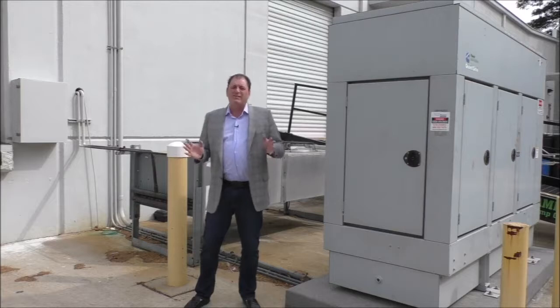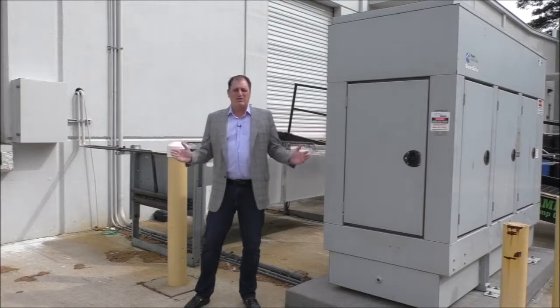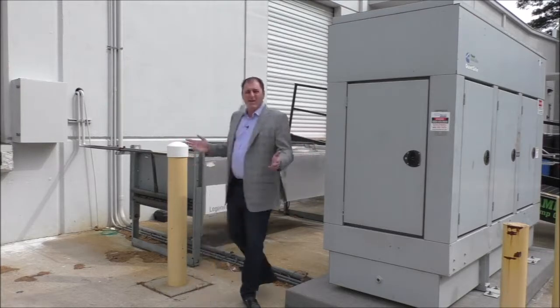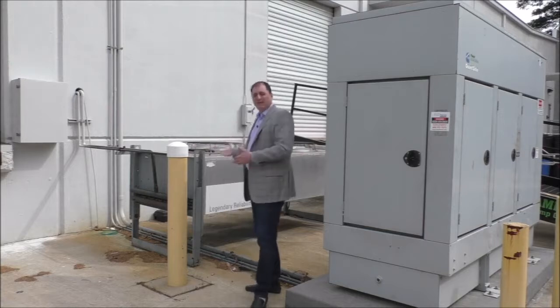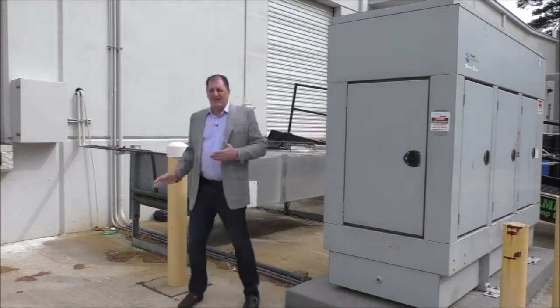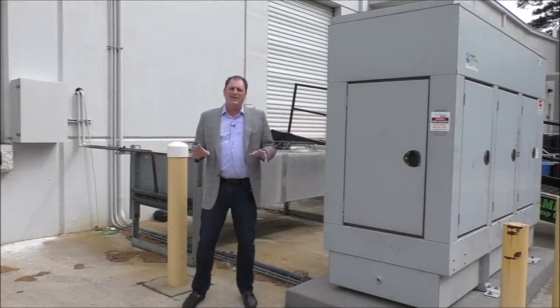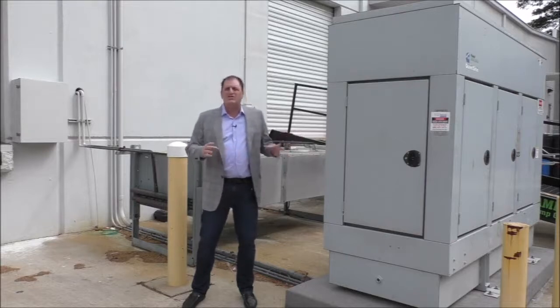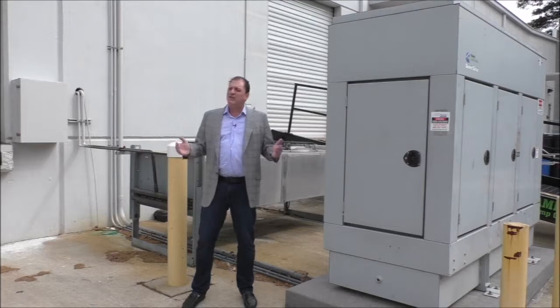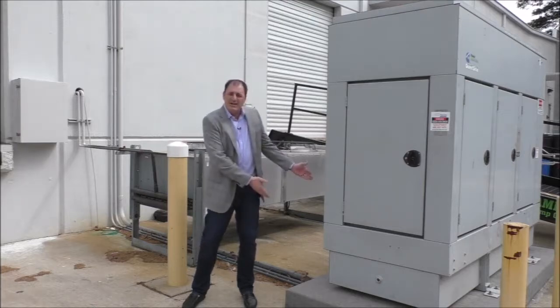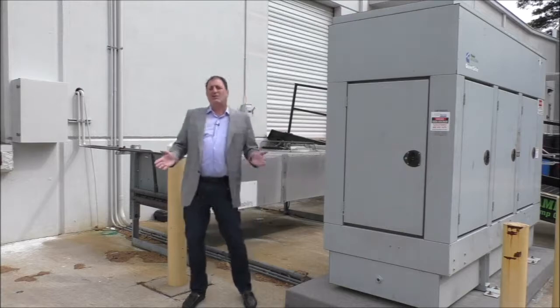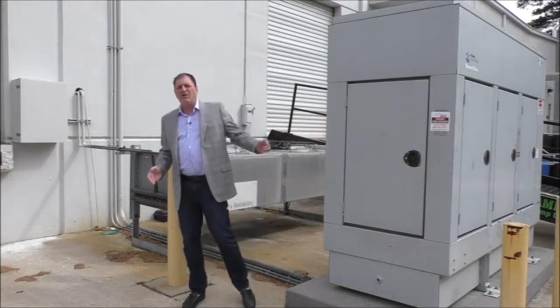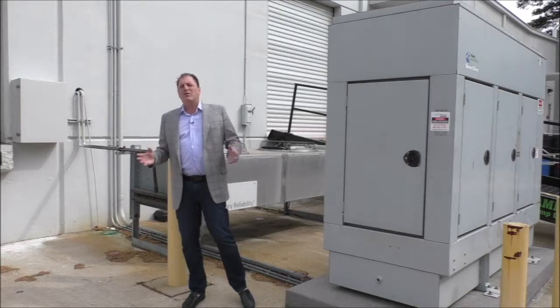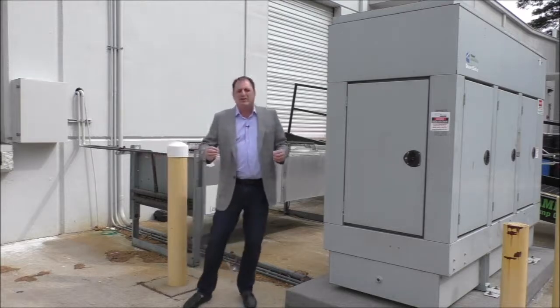The generator is sized to handle the entire data center, all of the lights, all of the office, all of emergency power, and all of the mechanical systems. For example, the outdoor heat exchanger, which we have powering the air conditioner in our data center. You may be asking why the UPS is the heartbeat of the data center when the generator can supply power for hours, days, or even weeks, depending upon its fuel source. I have a 24-hour sub-base fuel tank on this carrying diesel fuel. I could also have a propane tank external to the generator, or I could have a natural gas line, which would theoretically give me unlimited power while I wait for utility to come back.